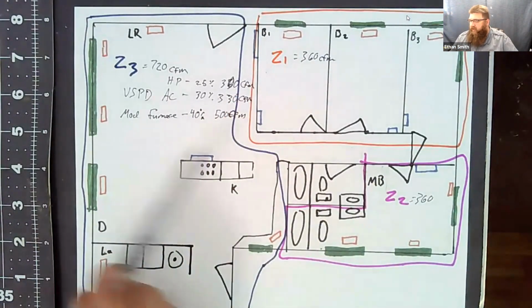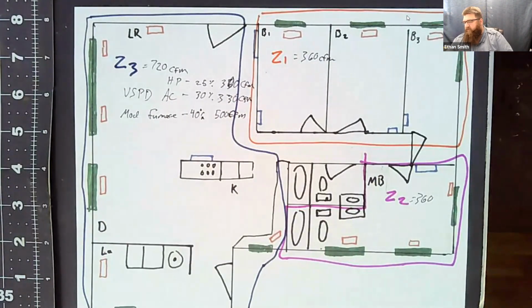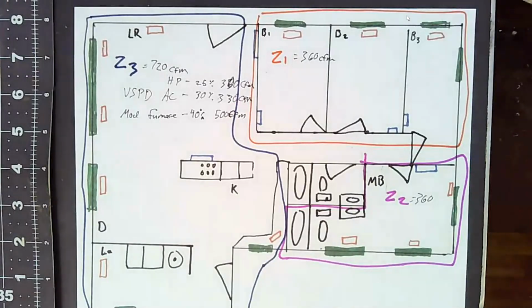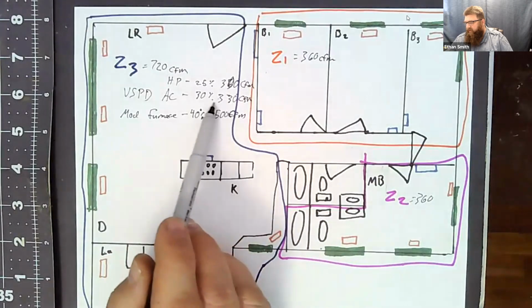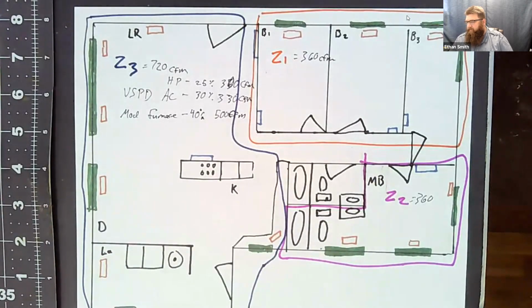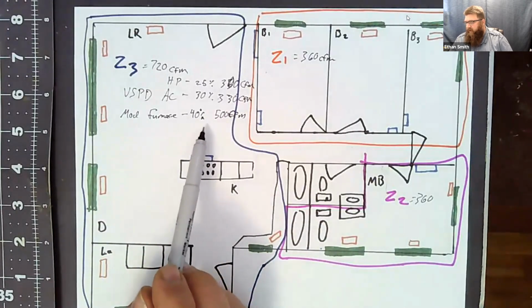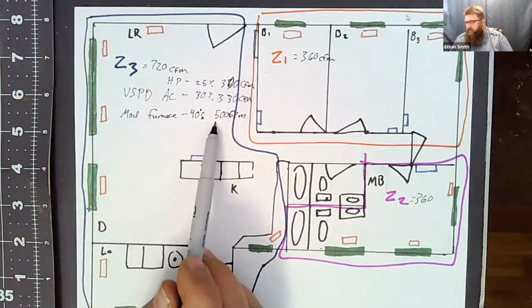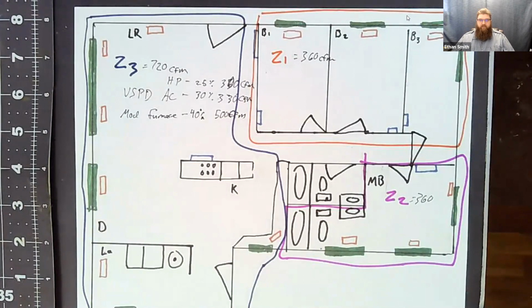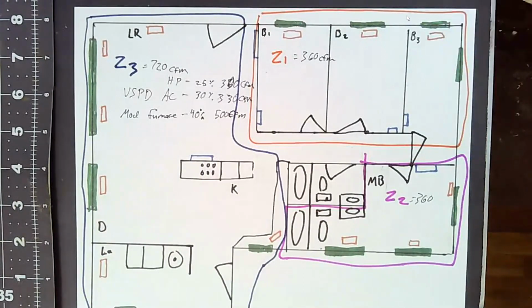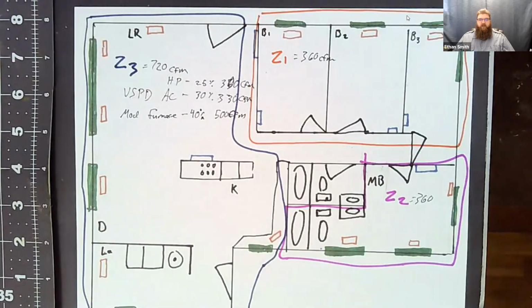So if I'm just running the AC, what happens when my smallest zone calls? Do I have an excess air problem? No, I do not, because all my zones require at least 330 CFM. Okay. What about on my furnace? My modulating furnace has a minimum airflow requirement of 500 CFM. What happens when my smallest zone calls? You have excess. I do have a little bit of excess there. So I'm going to have to manage my excess air in that case. That's not insurmountable though. That's only a 30% excess air for my zone size. So we could deal with that through one of our management strategies that we'll talk about in a little bit.